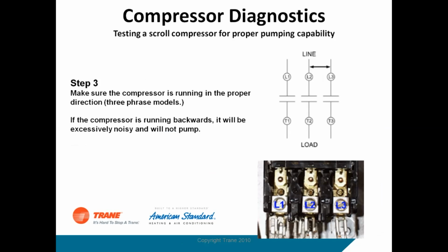On three-phase scroll compressors, again, make sure the unit's running in the proper direction. If the compressor is running backwards, it will be excessively noisy, and I'm sure you guys have all heard that. That's why we put phase monitors on all of our commercial equipment now, to make sure we don't run a compressor backwards. They don't last very long when you run a scroll compressor backwards. They've got to be in the right rotation. If it is in the wrong rotation, reverse any two wires, L1 to L2 or L2 and L3. Any two wires will change the rotation of a three-phase contactor. And again, look at the contactors. Make sure the contactors are good. Make sure they're clean.